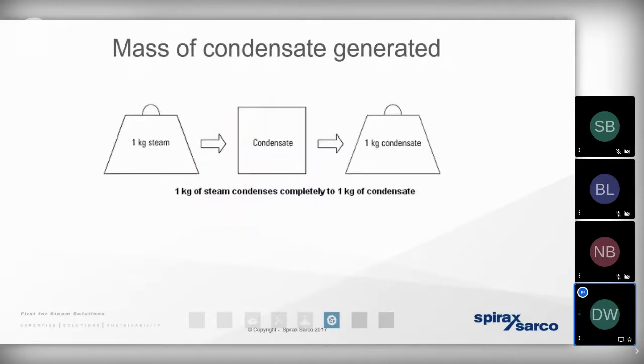Just to reiterate, if we put 1 liter or 1 kilogram of water into the boiler, it's going to change state and produce 1 kilogram of steam. And when that 1 kilogram of steam condenses, it's going to change state from a gas to a liquid, but the mass will remain exactly the same. That's why we always refer to steam distribution systems by mass flow rate, because a kilogram of steam will equal a kilogram of condensate. But what changes is the volume. That volume is dictated by whatever pressure we're generating the steam at in the boiler, because that's going to determine the volume of the steam.